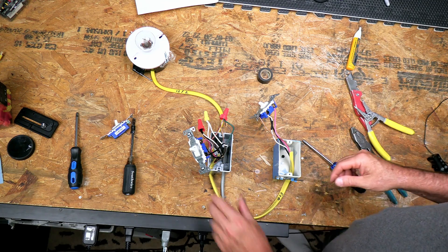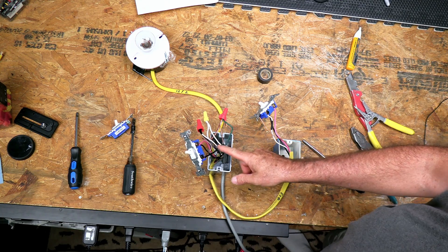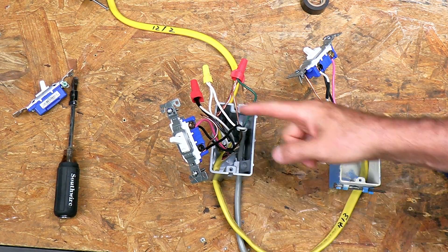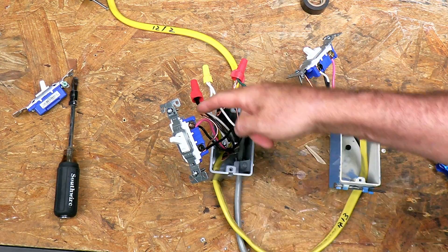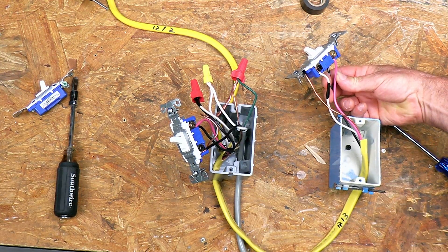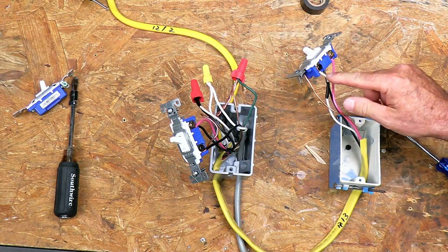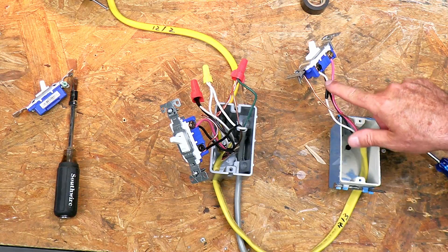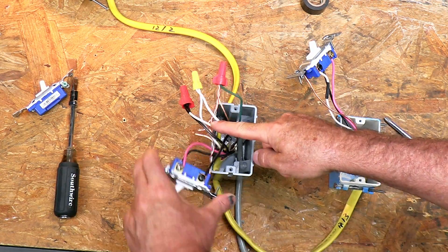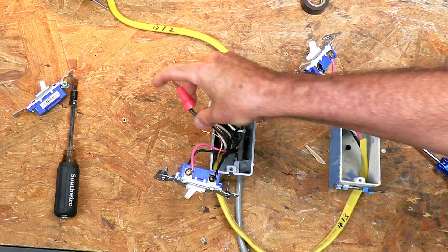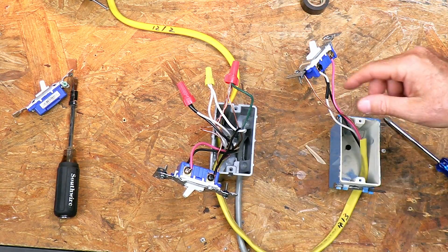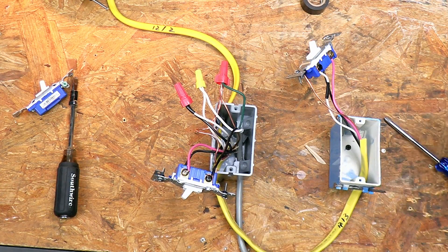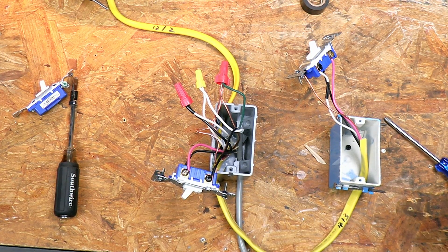So I hope that made sense. So basically, we have our hot coming in to our first three-way. This is our original switch location. That power is leaving on the travelers. Depending on the position of the switch, it's coming over here on the travelers. And then it's leaving on the black screw when we turn our switch on, on the white wire. Coming back here on the white wire. And then that is going to our light. So that's it. Our commons are tied together and our grounds are tied together. They don't affect the circuit. So I hope that all made sense. I hope this video was helpful.